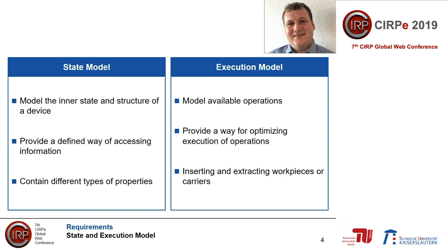First, it must model the current state and the structure of a device. The state model must express where carriers or workpieces are currently located within the facility, whether any resources are missing and need replenishment, where exchange points are to insert anything into the device, and how the different building blocks of a complex device are related to each other. The state model must provide a defined way of accessing the information. It needs to provide three different kinds of properties: properties exchangeable during runtime with no fixed value at start time stored persistently; properties that change during runtime but are set to a fixed value when loaded; and constant values that don't change during runtime.